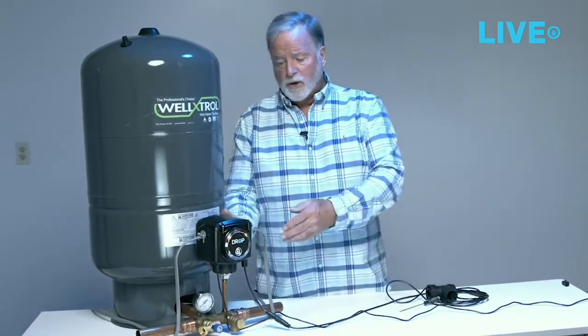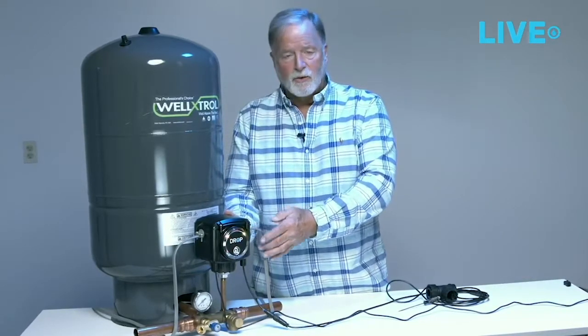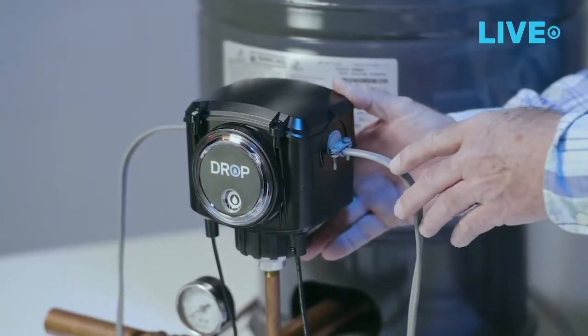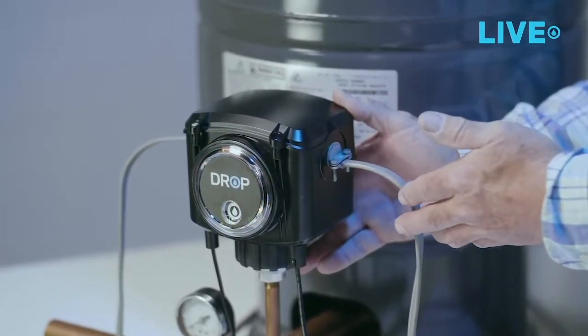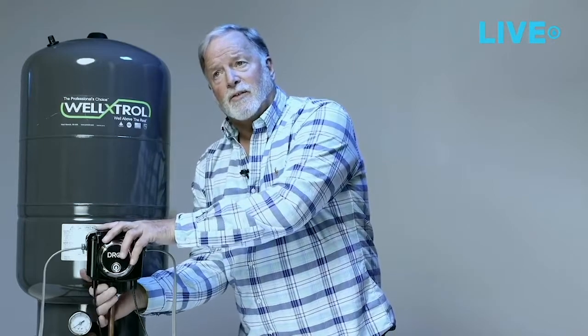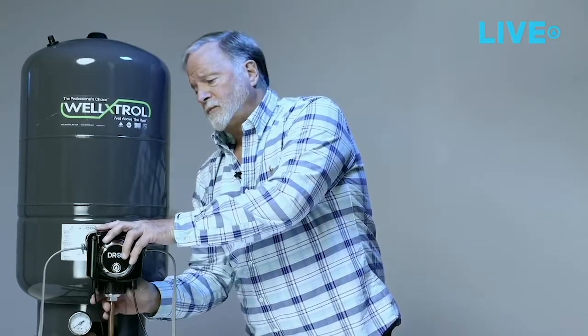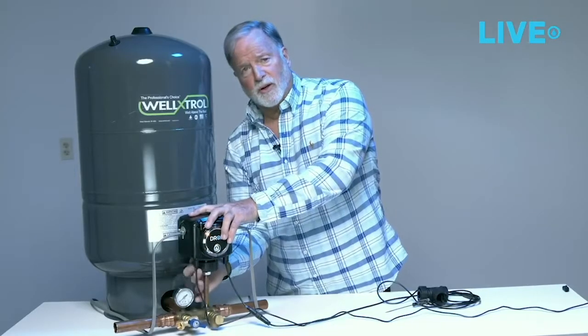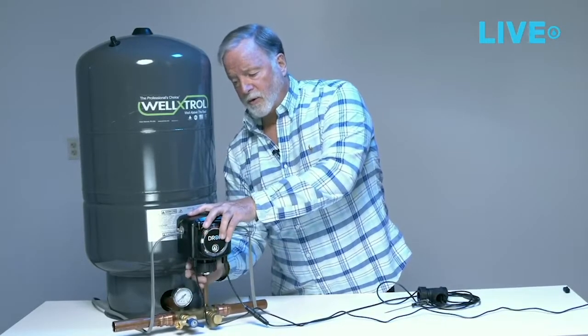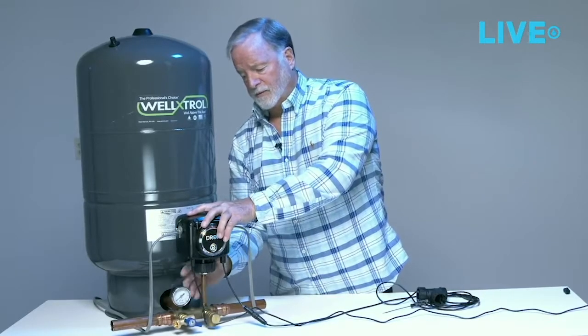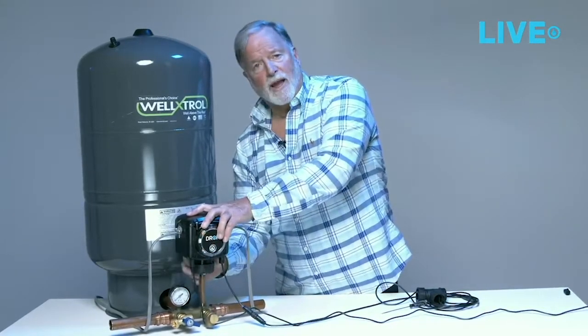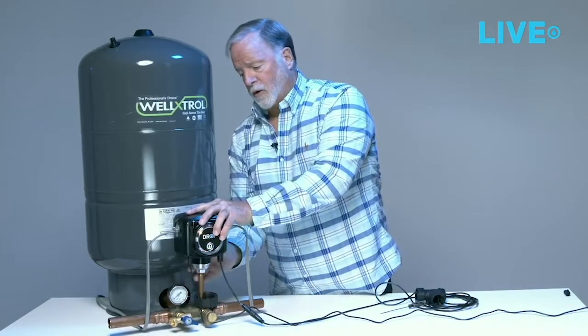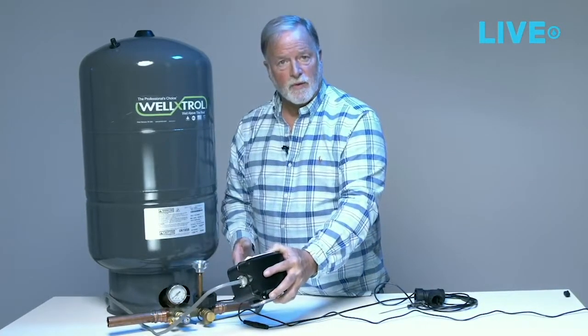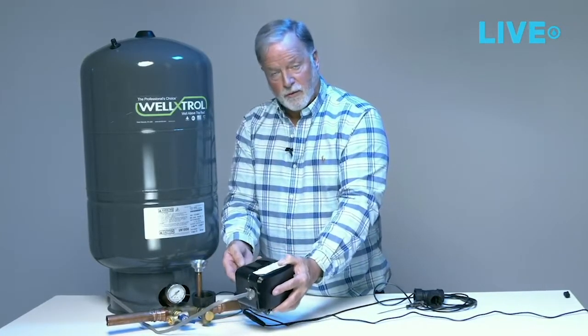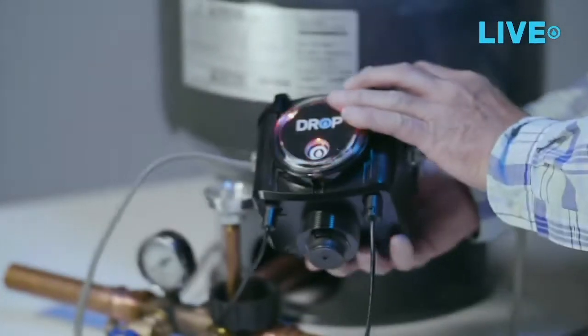In this application, we are showing a UFNM style cable, which you might or might not see, but it would be the same if we looked at an MC or a rigid conduit. And the main feature that this has with regard to the electrical connections is that it has this built-in union connection that houses the pressure transducer, which will allow the switch to be lifted completely up vertically if you would have a plug in the pressure sensing level. So without having to unwire the unit, you could pull it loose, service the pressure device, which I'll turn to the camera here and show you.